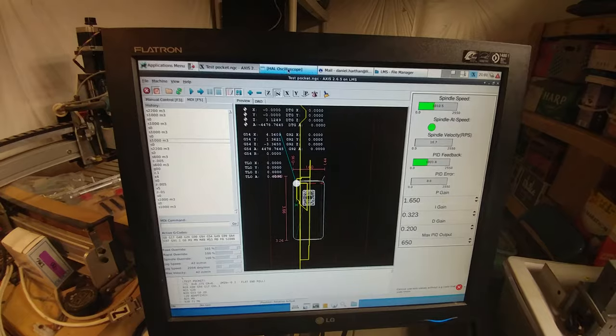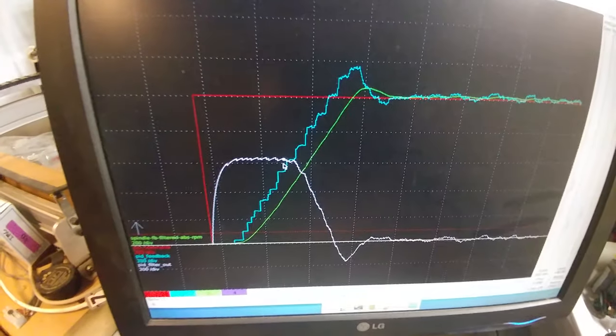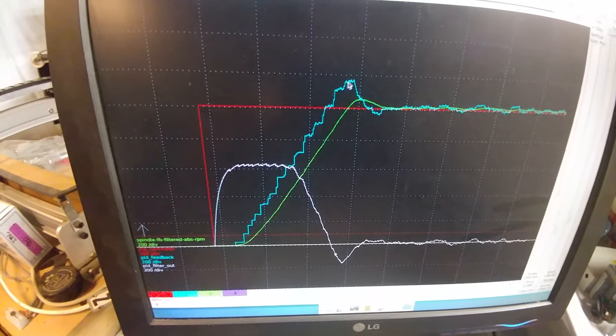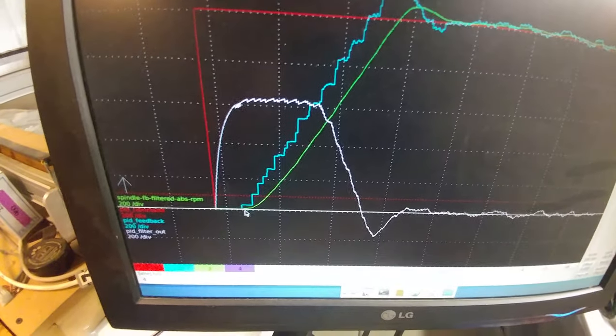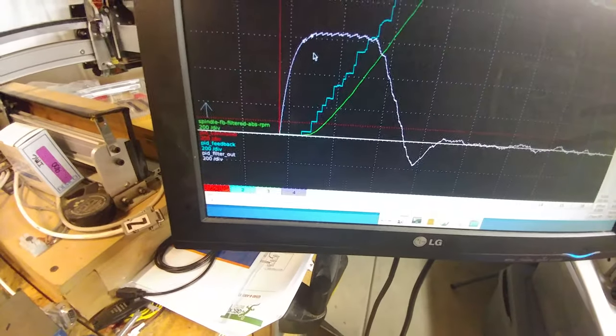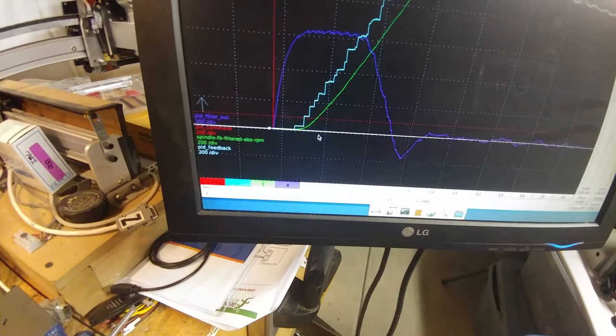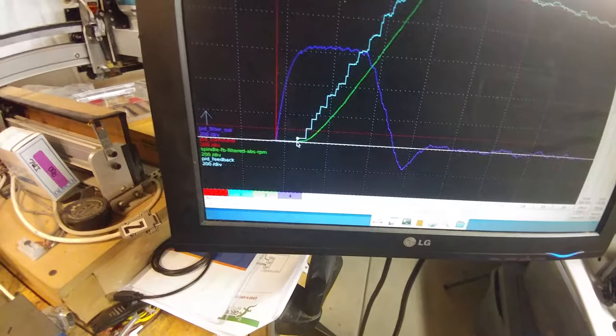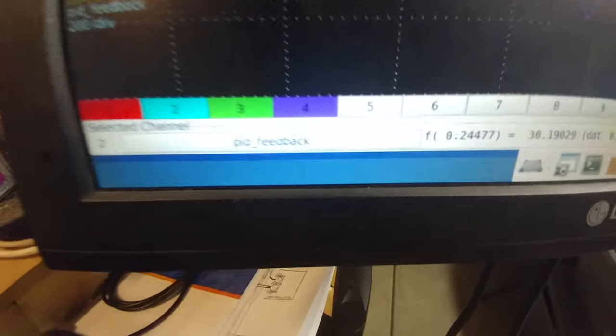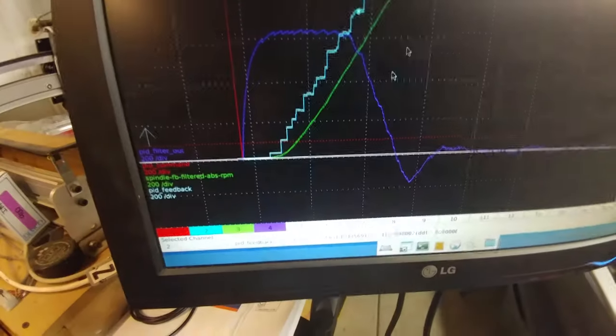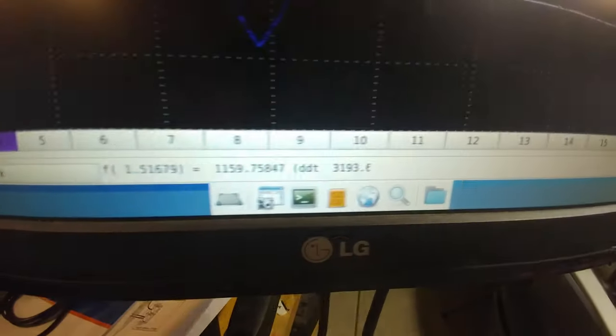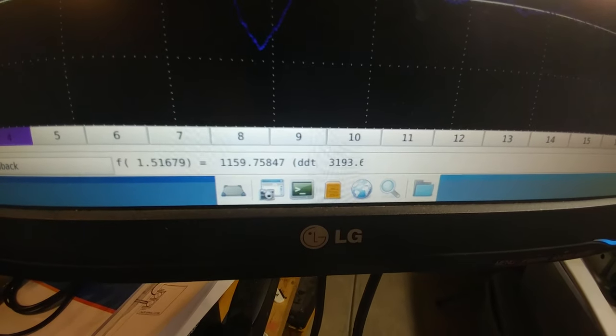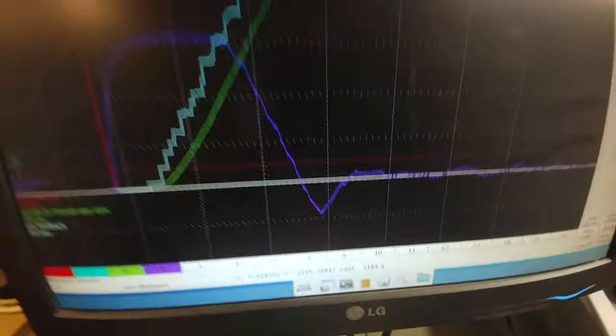There we are on our halscope. It looks like an overshoot. This one is about 180. It comes back to—let's select right there where it starts seeing everything. That's about 24 milliseconds of delay right there. If we go up to see the overshoot, we're at command at a thousand and it's 1159 at the high point there, so 159 RPM over, which is okay.